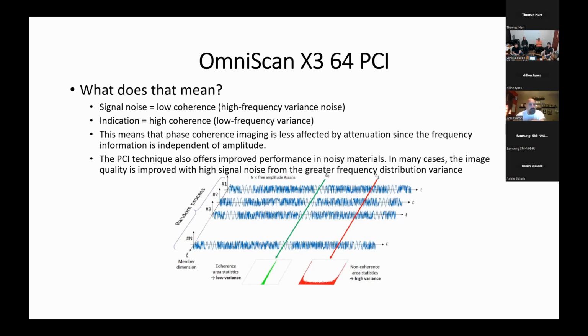It doesn't return back at the same frequency. We call that low coherence. It kind of takes it off the screen, reduces it. You don't really see a whole lot of signals from those low coherence reflectors inside the material. When you have indications, though, you tend to have what's called high coherence or low frequency variance. So the response signals from those indications tend to be rather close in frequency, which means that they're coherent. And what our algorithm on our machine does with that is it brings those indications out so you're able to see them better. It also offers improved performance in noisy materials. In many cases, the image quality is improved with high signal noise with a greater frequency distribution variance.